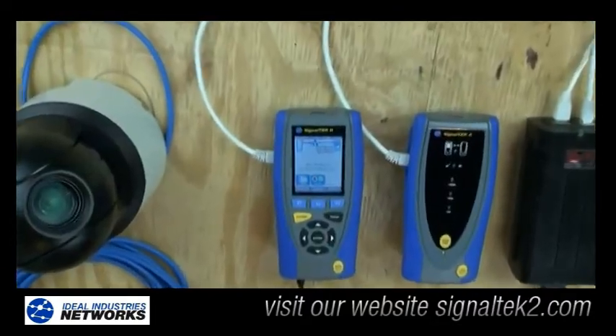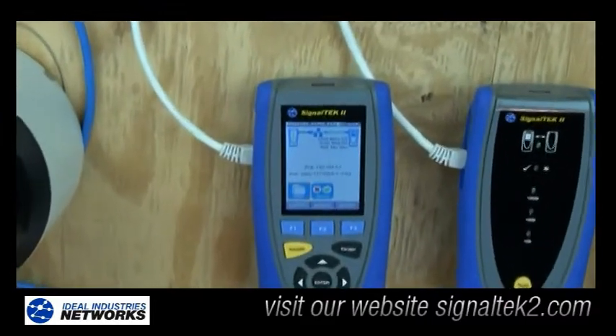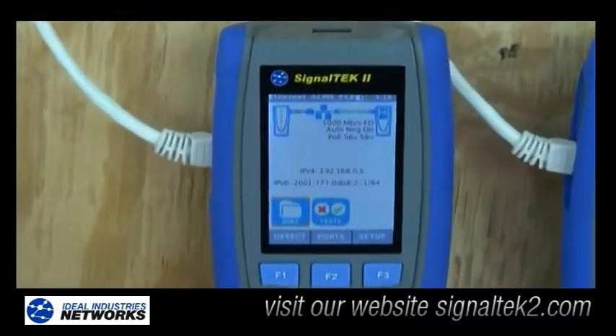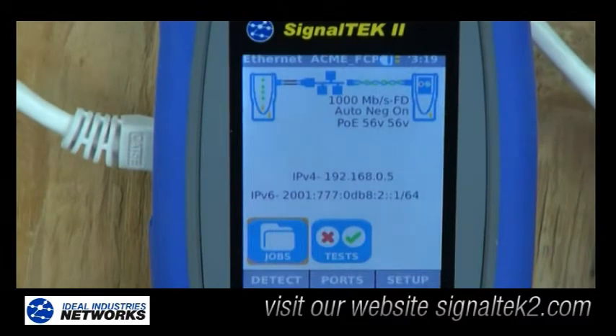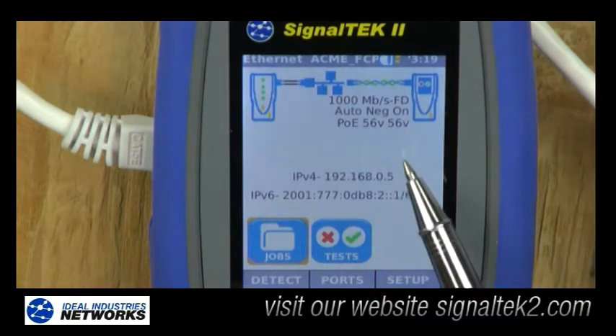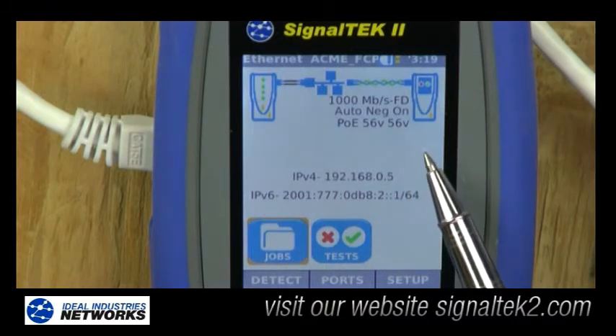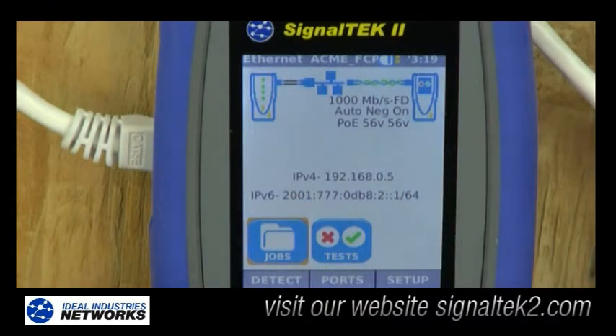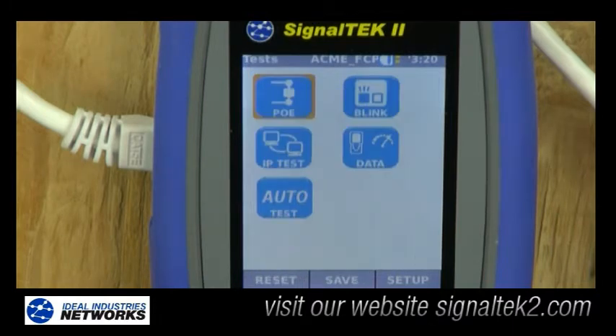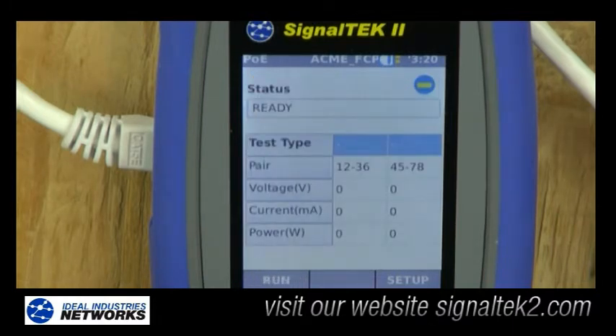Here's a close-up view of the Ideal SignalTek2 tester. Power over Ethernet is the most common method for powering IP cameras, and some require higher PoE+. And testing and troubleshooting can sometimes be a little bit of a challenge. SignalTek2 tester can actually help you out in a couple different ways. First, on the home screen, you'll know if PoE is actually available because it shows it to you right there on the screen. Now, additionally, you can actually test that PoE source to determine actually how much power is available, which is kind of critical in making sure this camera is actually going to work.